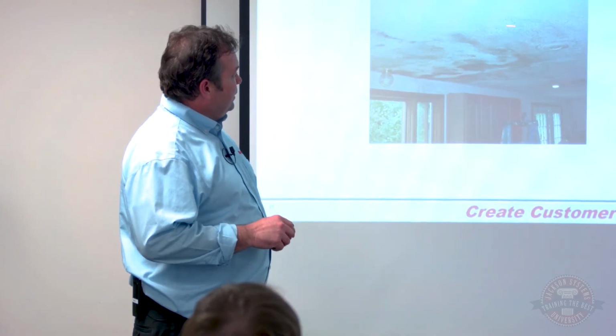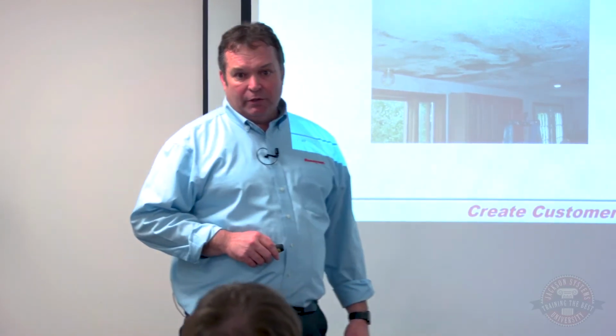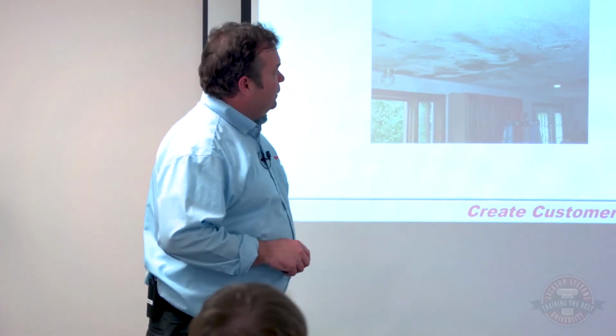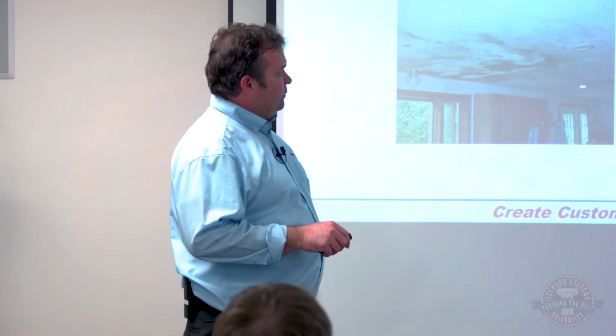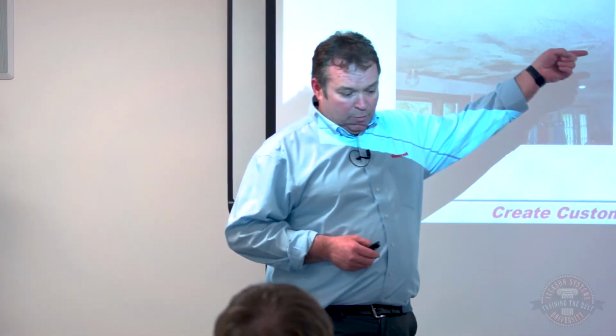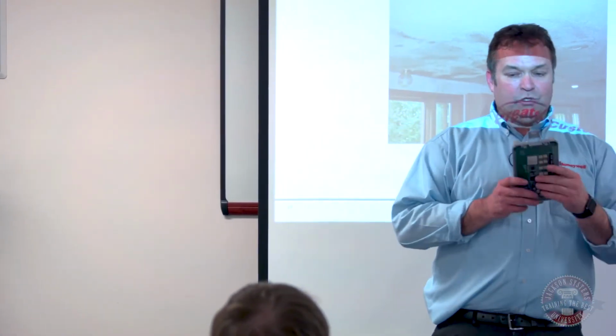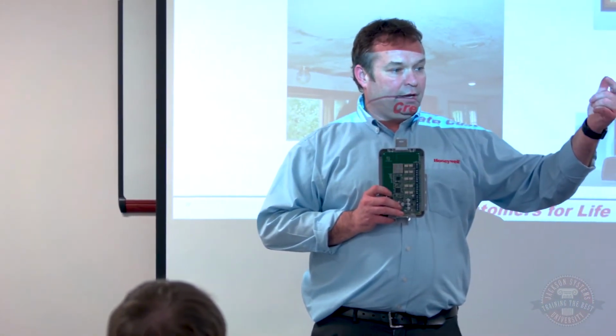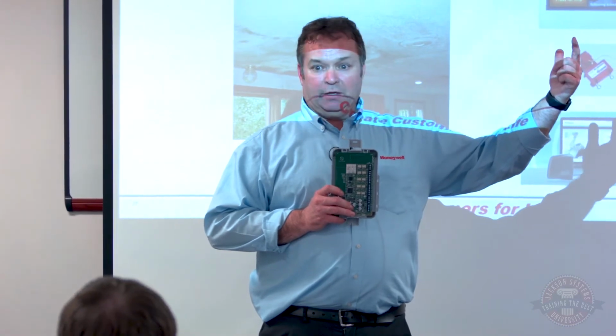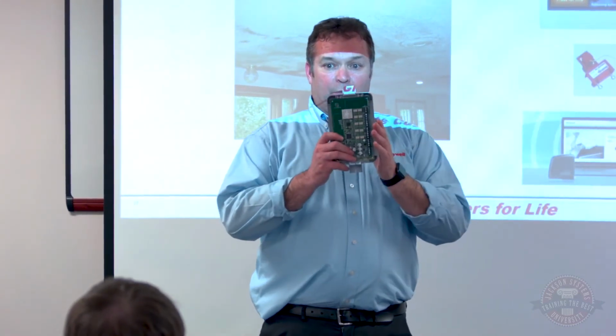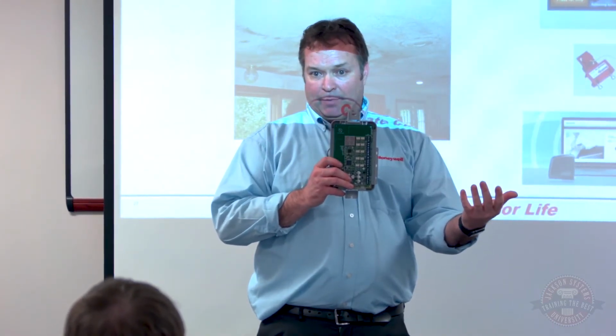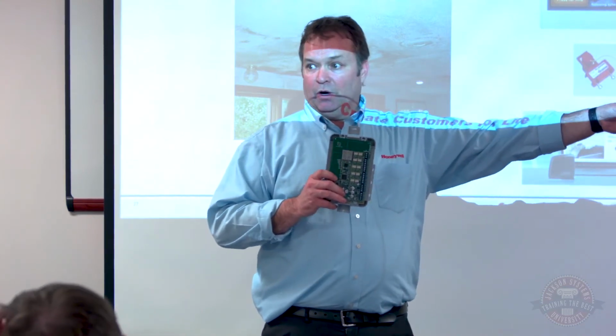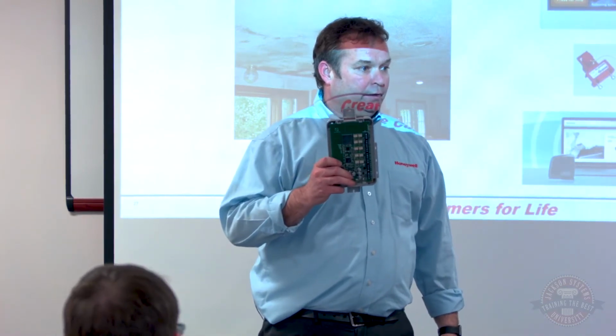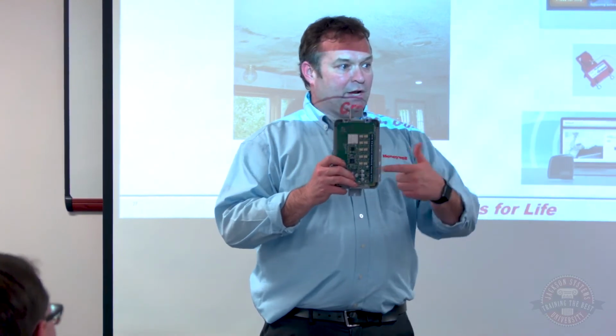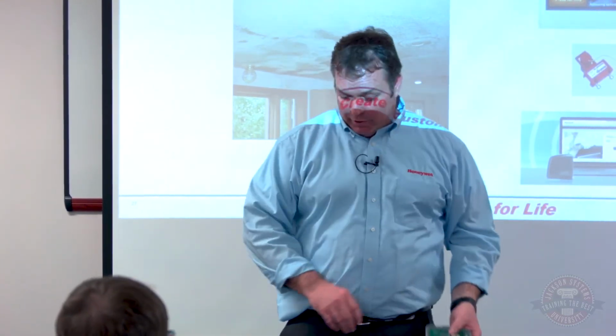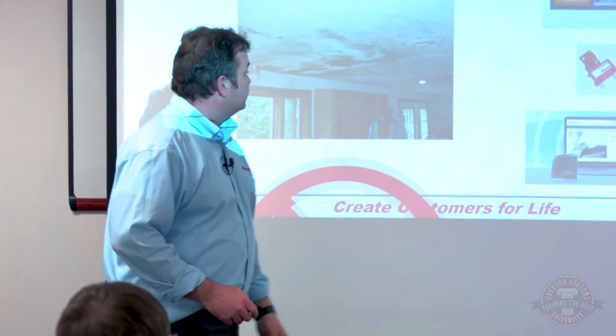This is a big nasty mold spot from a drain pan above the ceiling that leaks. So if I just had that float switch hooked to the Prestige, I can choose system shutdown, and instead of just cutting the power, it would stop the heating and cooling from happening and email the customer an alert without killing the power. So you'd take your normal float switch, tie it into this, get an alert, and you know you've got an issue you need to fix.